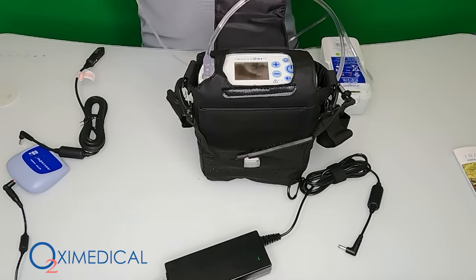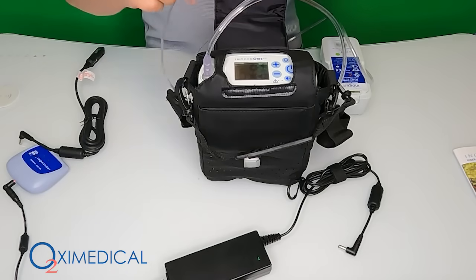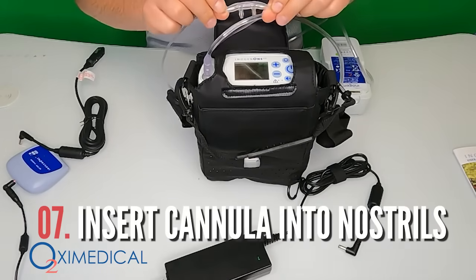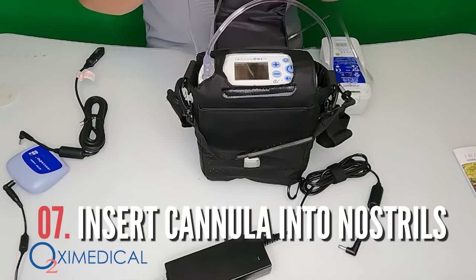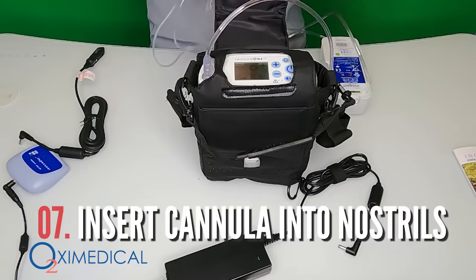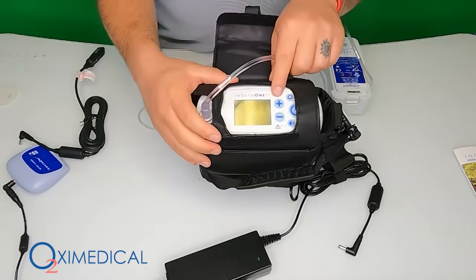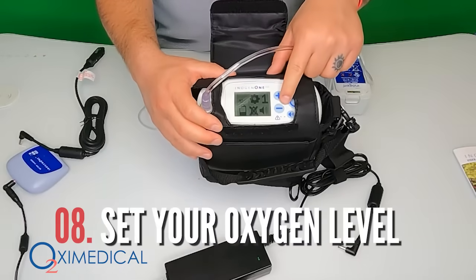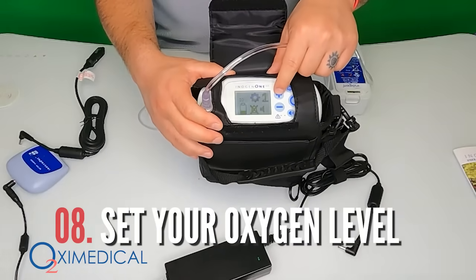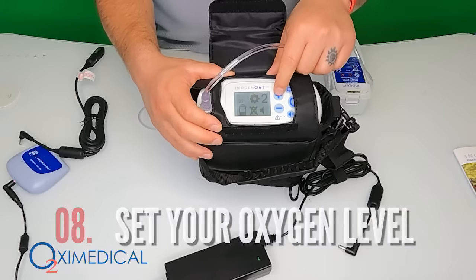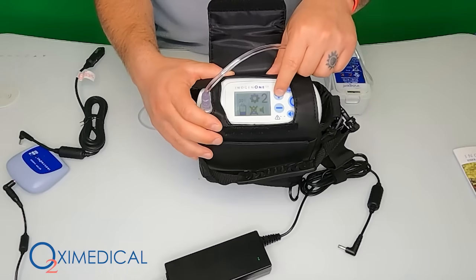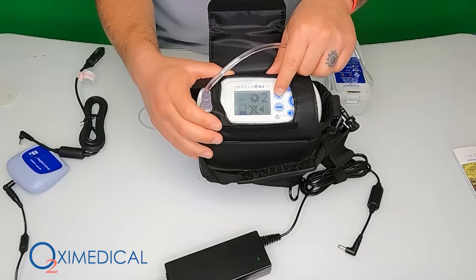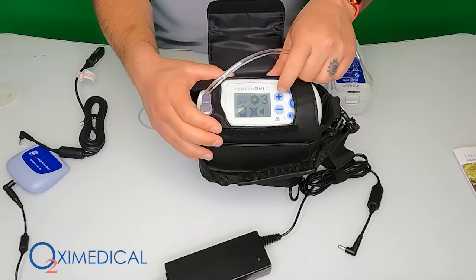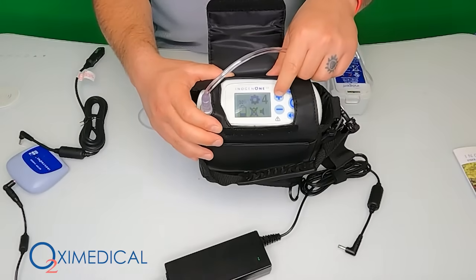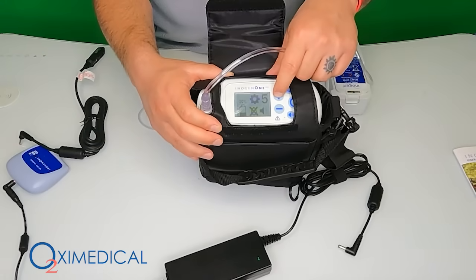Once this is on, you line up the tip of the cannula, put it over your face, and you're just good to go and taking breaths as so. To increase the oxygen setting, we have the plus and the minus. This plus will go up. Every time I touch the button, it gives me a little beep to let me know that it registered me pressing it. And this will go all the way to a setting 6.